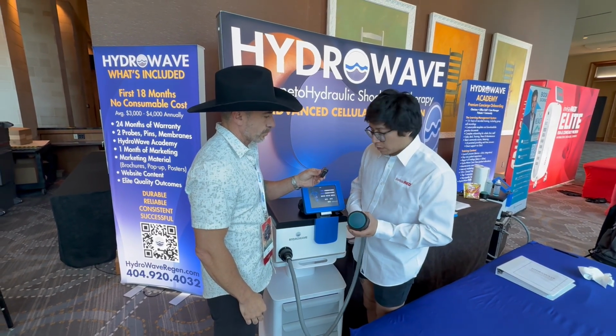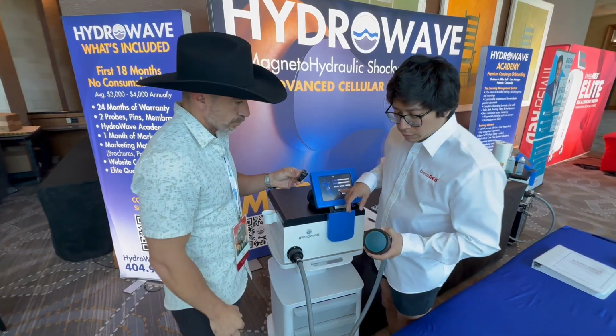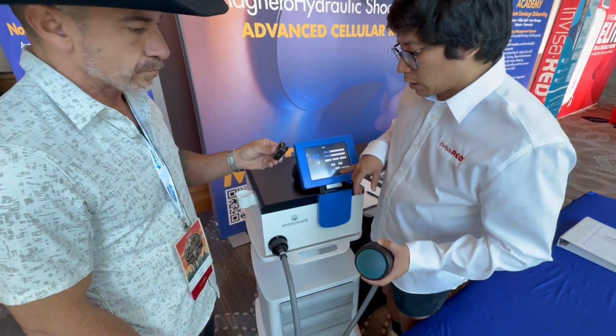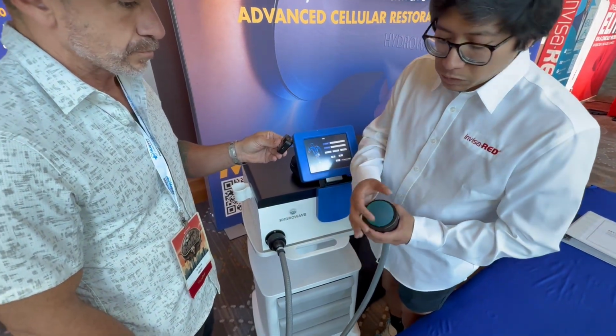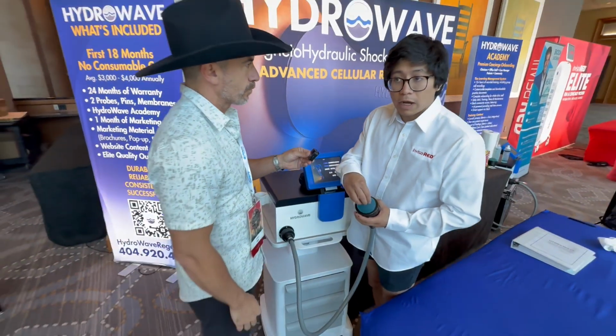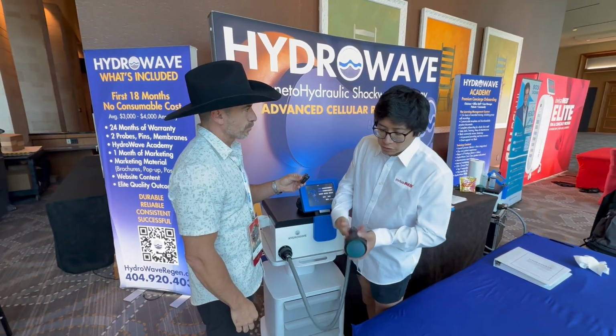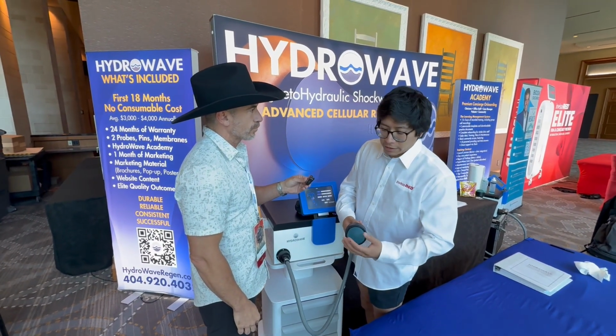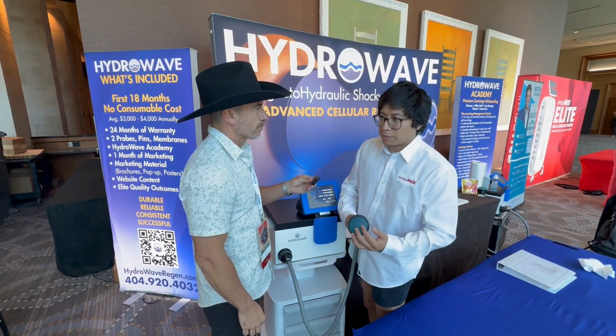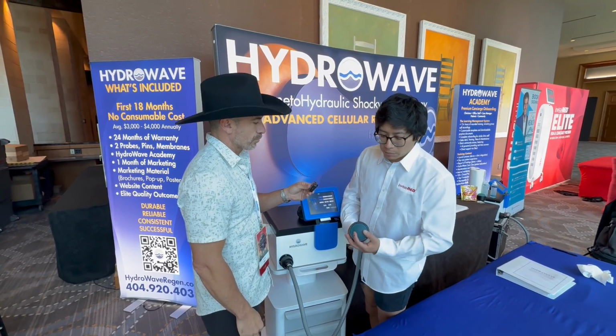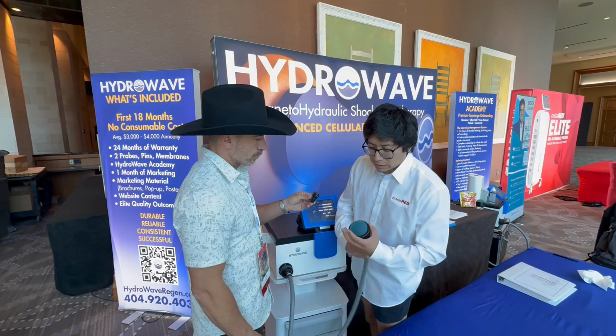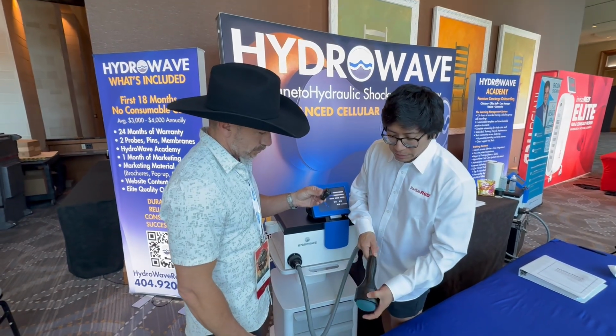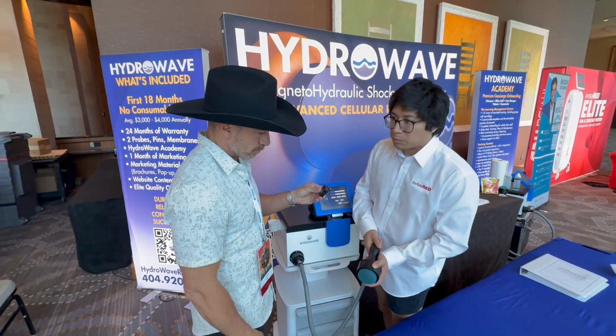If you still get a little bit of air bubbles, just go ahead and fill it up as much as possible. You'll just turn it on for a bit, and then all the air bubbles will most likely be centered at the top. If that bubble is at the top and you're trying to do a treatment, then that itself is causing the shockwave not to get there. So once the bubbles are there, just tilt it again at that 45-degree angle where this pin is, and then just suck all those air bubbles out.